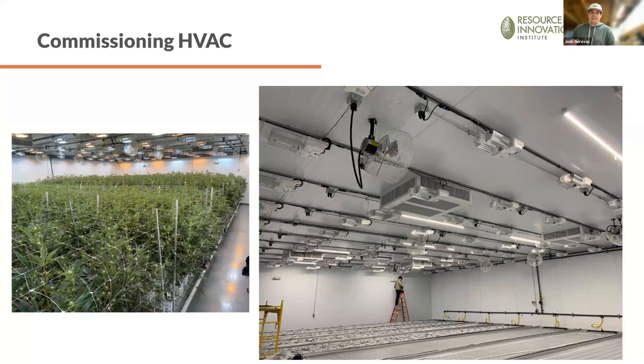This facility specifically, I caught the first night we went to lights off - I'd say it was week 2 of flower. I was luckily in the facility and caught it: our electric reheat failed and humidity was at 100% for an hour. I had to get in there and really dig in to figure out what was going on, crawl up in the crawl space, and figure it out while on the phone with my HVAC engineer. If I wasn't there at that time, there could have been some big problems. So finding someone you can have on hand checking those things during the critical stages is really important.